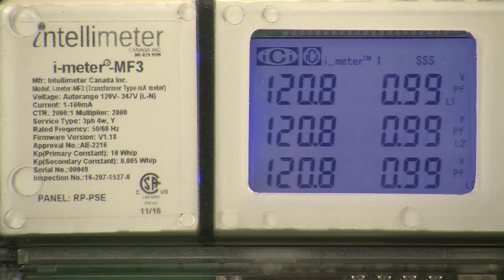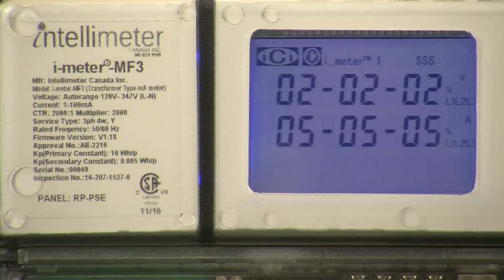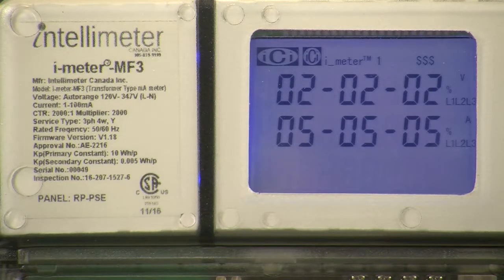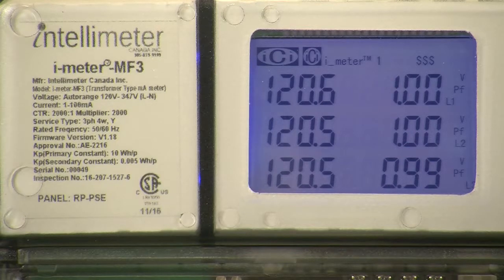So if all the information on the display looks normal, right away you can take a clamp-on amp meter and compare the amperage on the live feeds to the amperage being displayed on the MF3 meter. You're going to start with the information for line 1. Place your clamp-on amp meter on phase A main feed, or wherever else CT1 may be installed, and see if the information on the iMeter MF3 display matches the amps on your clamp-on meter.